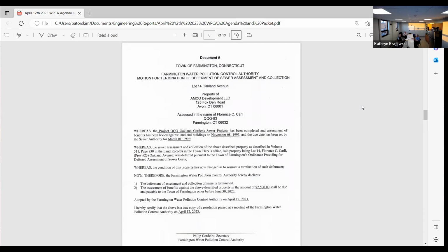So when we have capital improvements, we do them 4 times a year, and that goes towards the capital budget when we approve it. Russ and I have discussed, and the DPC engineering has already looked at the pump station by Orchard coming up South Road, just to take the head off of the pumps. Right now there's 248 feet of head. When we had the failure at West Farms, the volute was basically this thin from cavitation. When we went in, we had epoxy on the inside of the volute, and that was the only thing keeping it together. Everything else is just worn out from cavitation.